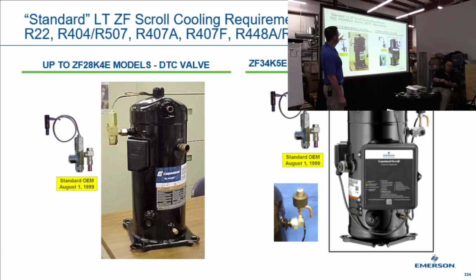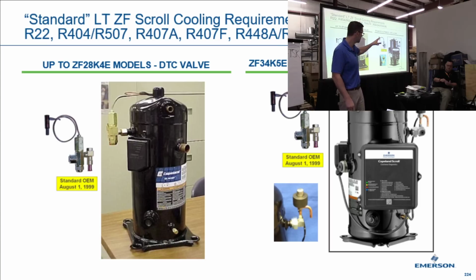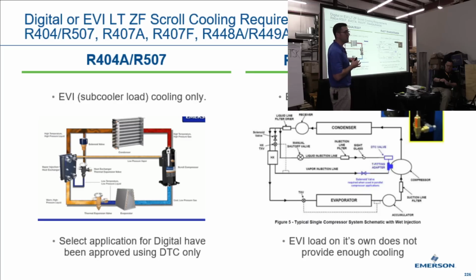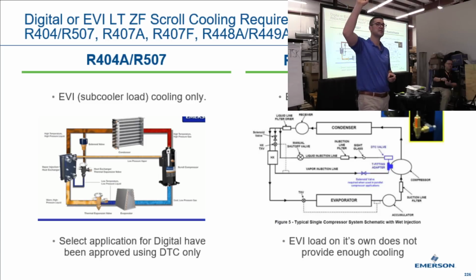Okay, DTC valves. So these are a temperature valve. So you got a temperature probe in the head, and when that temperature starts to rise, the valve will open up and inject some refrigerant in there to cool it down. Okay? We have electronic ones, and I don't know, they're not as popular. They should be, because they work amazing with electronic valves now on these ones for the DTC. So, anybody here heard of an EVI compressor? Enhanced vapor injection compressor? Show of hands.